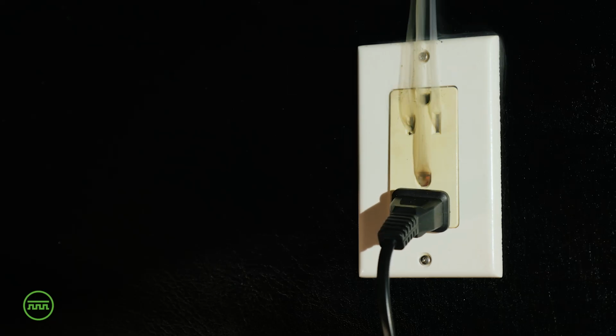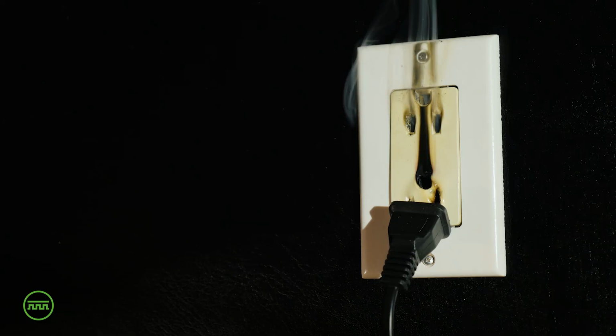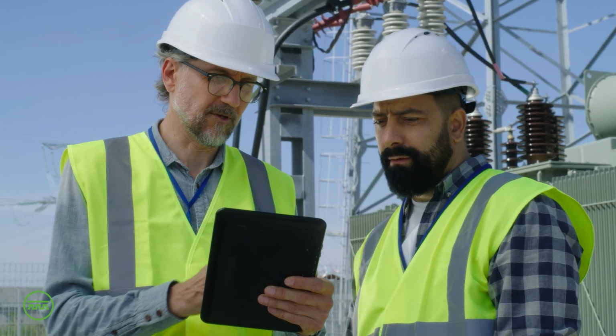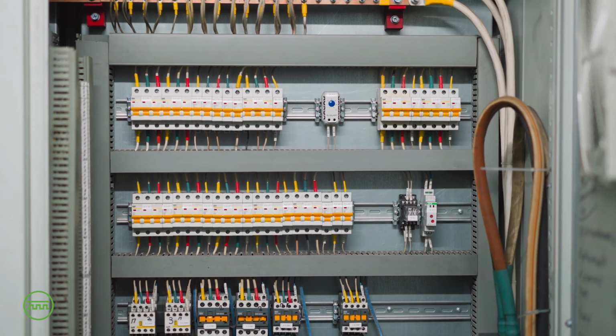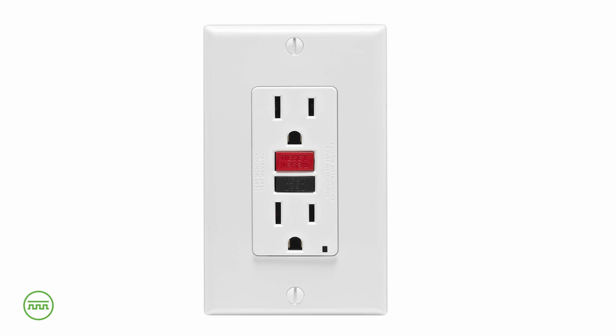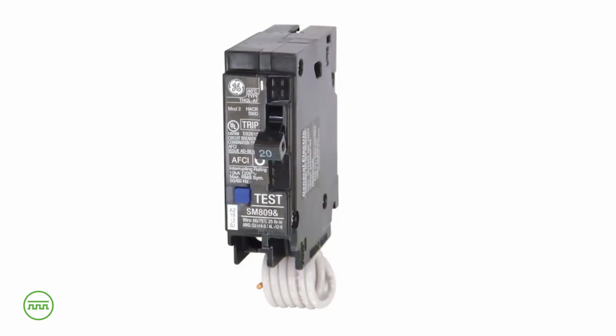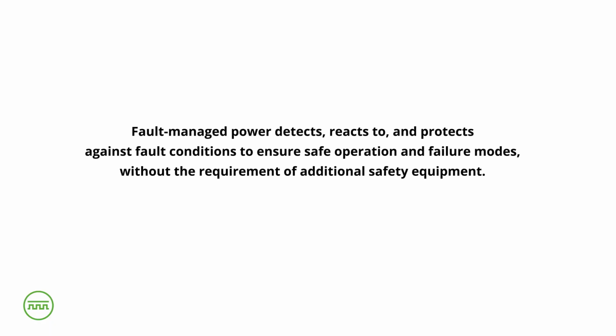To protect people from the dangers of AC power, the hazards found in conventional distribution systems are managed by equipment like breakers, GFCIs or ground fault circuit interrupters, and AFCIs or arc fault circuit interrupters. Unlike with current electrical distribution, these protections aren't needed for fault-managed power users. This is because fault-managed power detects, reacts to, and protects against fault conditions to ensure safe operation and failure modes, without the requirement of additional safety equipment.